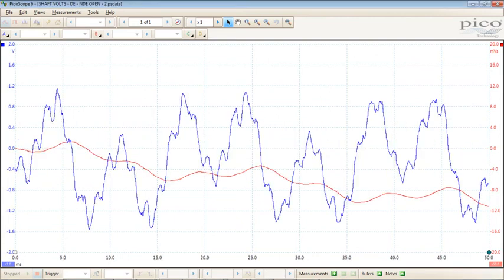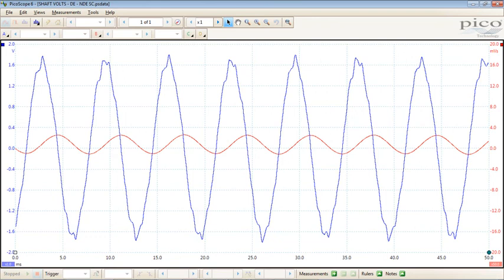Okay, then this is now direct online. So this is now a slow speed, quite a big machine. It's at about a 1.2 megawatt, 12 or 16 pole or something. I can't remember the details. In a test environment, and this is the shaft voltage measured from the shaft to earth directly. So what you can't see it here.